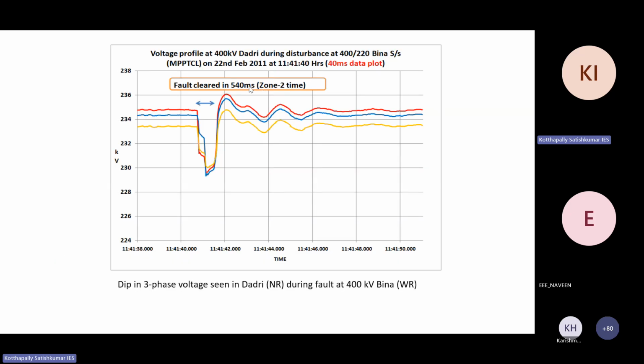The fault cleared in 540 milliseconds. Using this time, you can tell whether it is a zone 1, zone 2 or zone 3 operation. All these phase voltages went down together and went up together. So it indicates a three-phase fault.